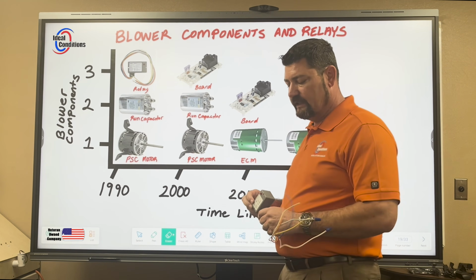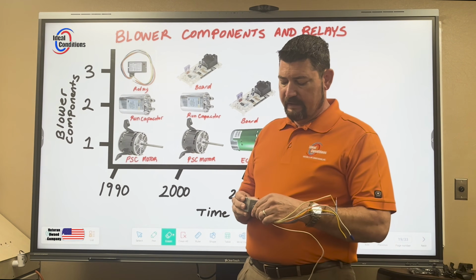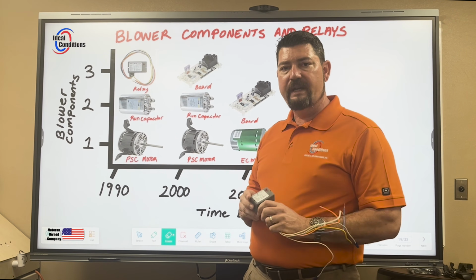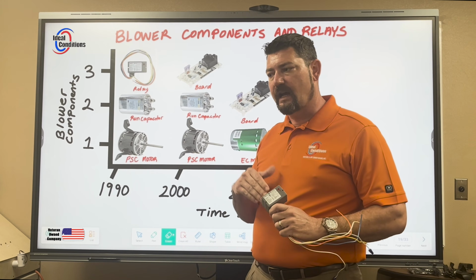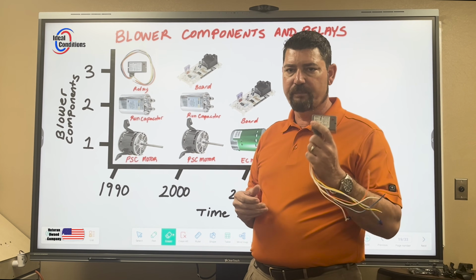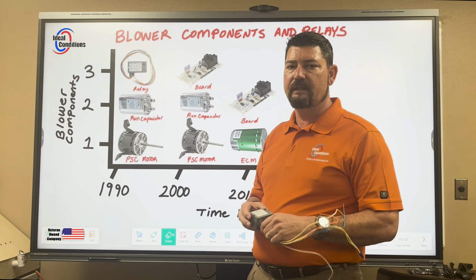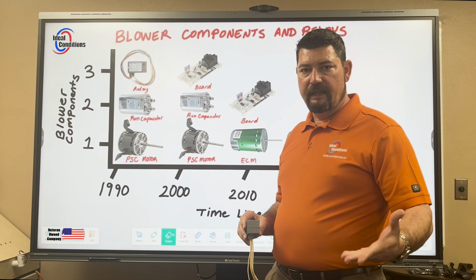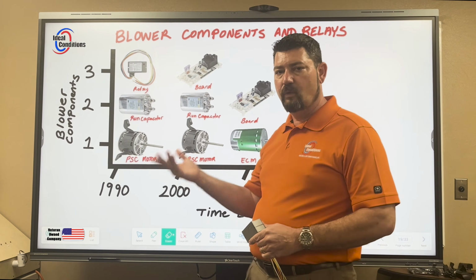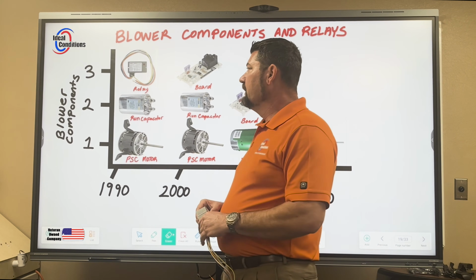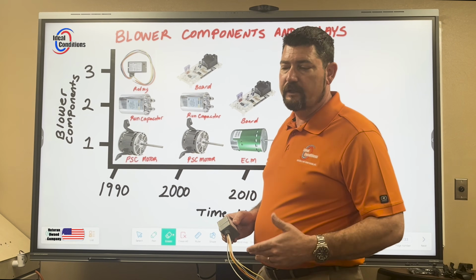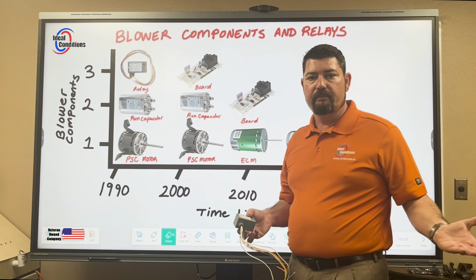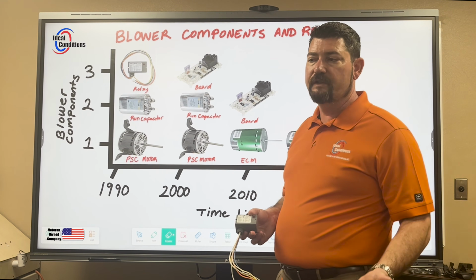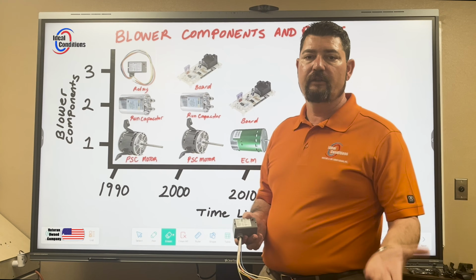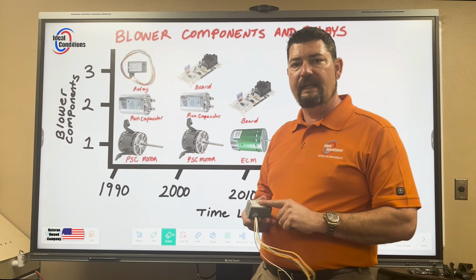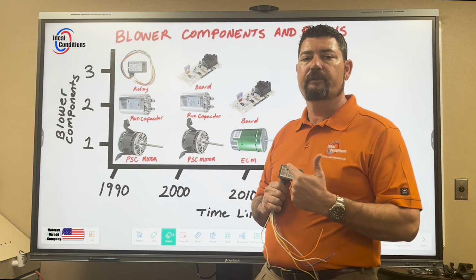It's a RIB relay that is very common. There is another one that has a higher ampacity. This one's pretty common for residential application. The one for 10 amps and below. The other one is 20 amps and below. If you buy the 20 amp and below one, you can use it for anything down to 1 amp. If you buy the 10 amp and below one, you can't use it for anything above 10 amps because those contacts aren't rated to handle that, and you might melt, cause a problem.